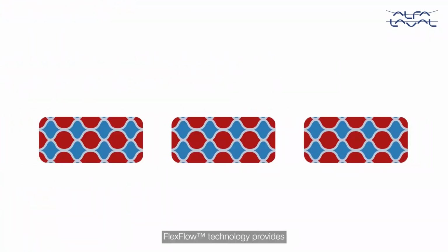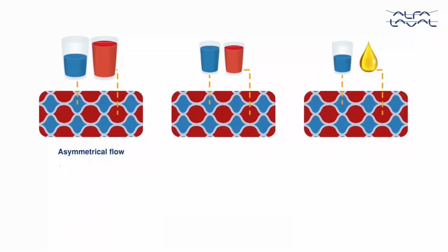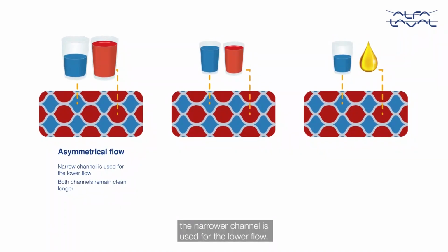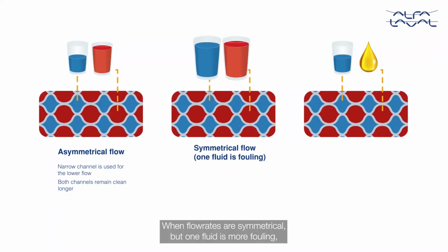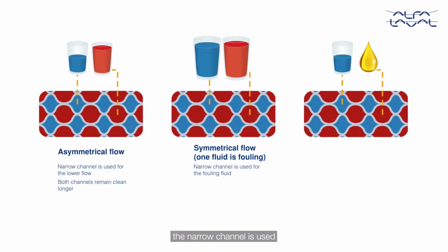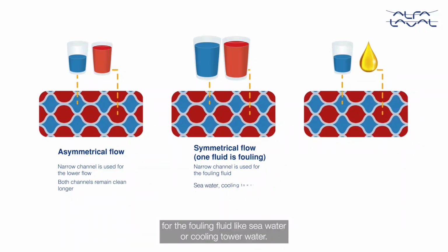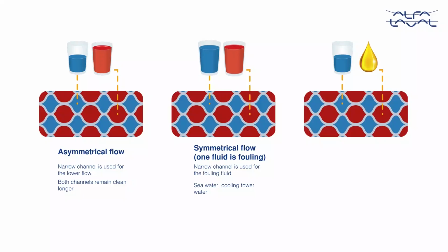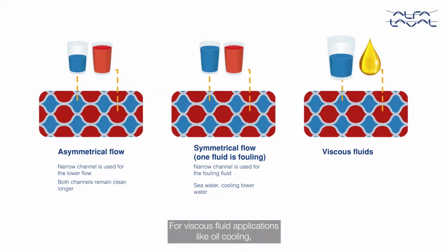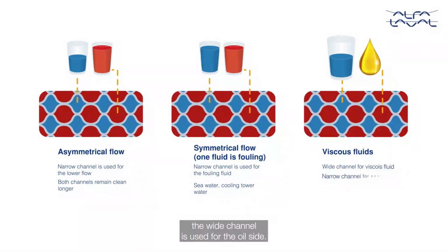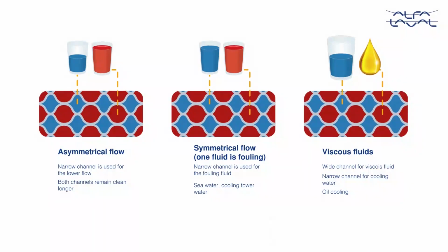FlexFlow technology provides savings for applications where flow rates are asymmetrical; the narrow channel is used for the lower flow. When flow rates are symmetrical, but one fluid is more fouling, the narrow channel is used for the fouling fluid, like seawater or cooling tower water. And for viscous fluid applications like oil cooling, the wide channel is used for the oil side.